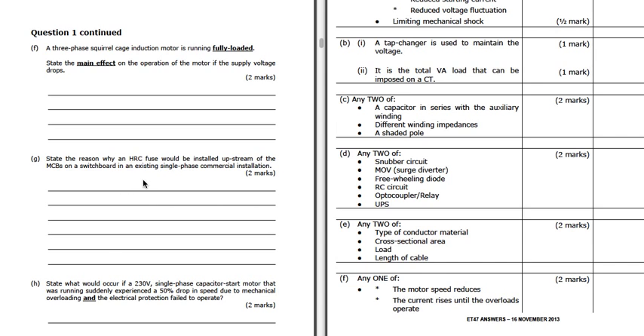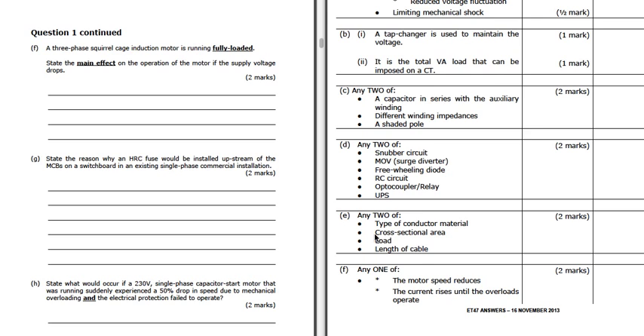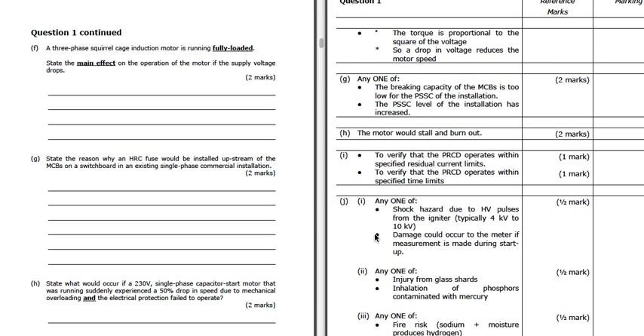G, state the reason why a HRC fuse would be installed upstream of an MCB on a switchboard. So an MCB hasn't got the rupturing capacity of an HRC. So if we've got a very high fault current, a prospective short circuit fault current, then we need this HRC fuse in there that can safely interrupt that big current. So G there, the breaking capacity of the MCB is too low for the PSSC, prospective short circuit current of the installation. That could be one instance, or if the level is increased for some reason, then we might need to put that HRC fuse in.